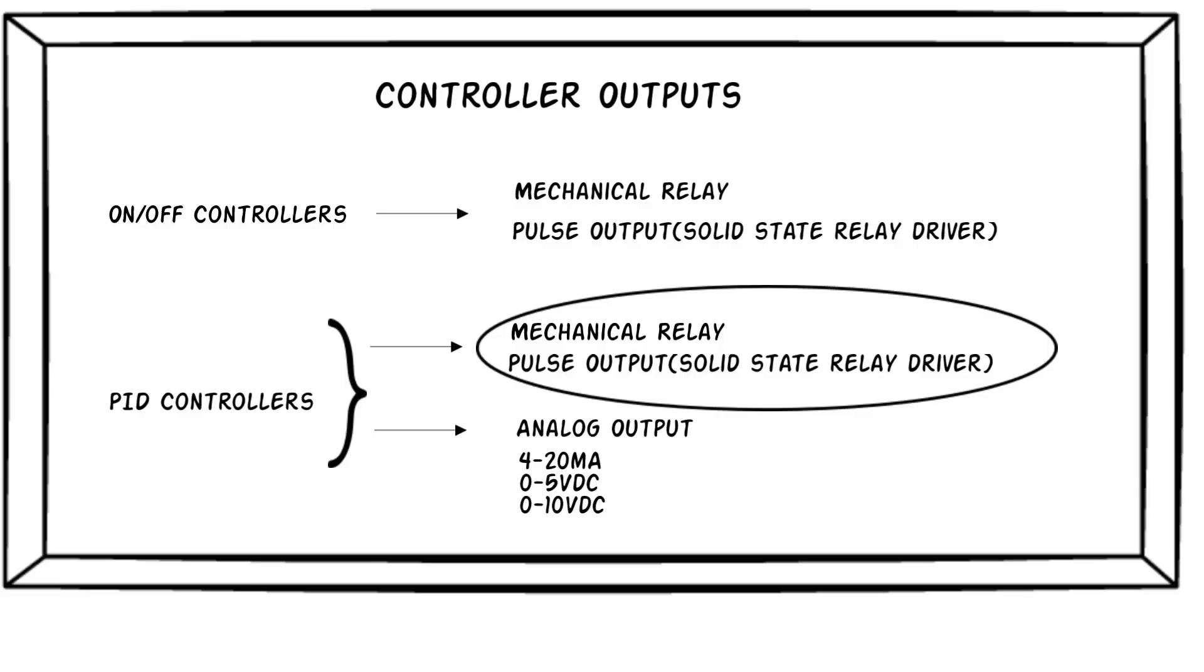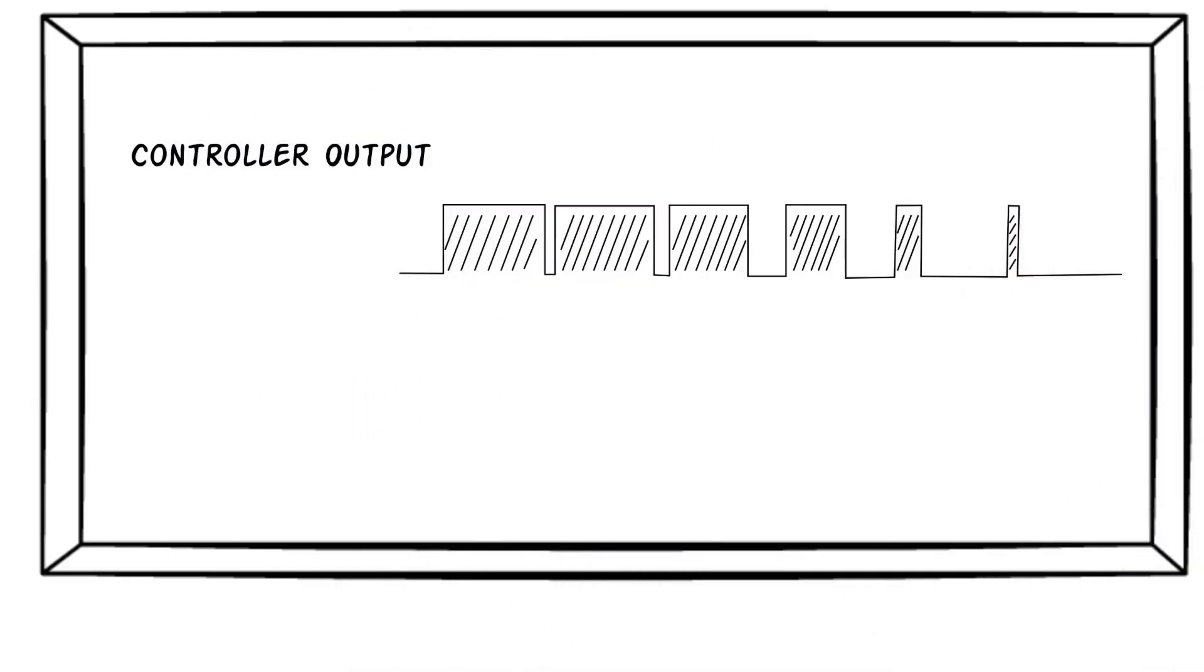As we discussed in the previous slide, with on-off control, the output is on when the temperature is below the setpoint and off when the temperature is above the setpoint. With PID control, rather than simply switching the output from one state to another above or below the setpoint, the output of a PID controller is cycled on and off.